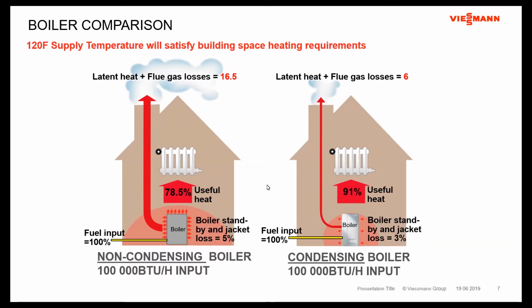But sometimes you see energy savings when you pull that non-condensing boiler out and put a condensing boiler in, a 30-40% energy savings. And this is kind of where that starts to get aggregated when you start looking at the standby losses as well as the operational losses of that boiler over an annual period. It might only be a 10% AFUE difference in the boilers, but as far as operation, you can get 30, 40, 50% difference in energy between the two of them.